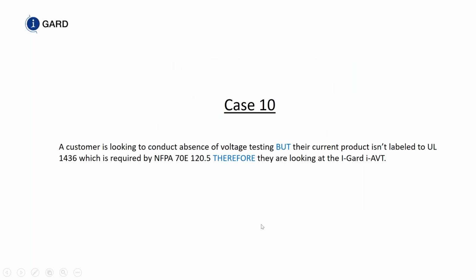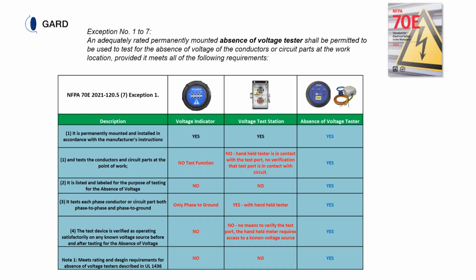So case 10, a customer is looking to conduct an absence of voltage test, but their current product isn't labeled to UL 1436, which is required by NFPA 70E. Therefore, they're looking at the I Gard absence of voltage tester, the IAVT. In prior revisions of NFPA 70E and Z462, you were allowed to have just a permanently mounted device to monitor voltage. It has changed in 2021 and 2020, whatever the latest revisions are, to a permanently mounted absence of voltage tester.